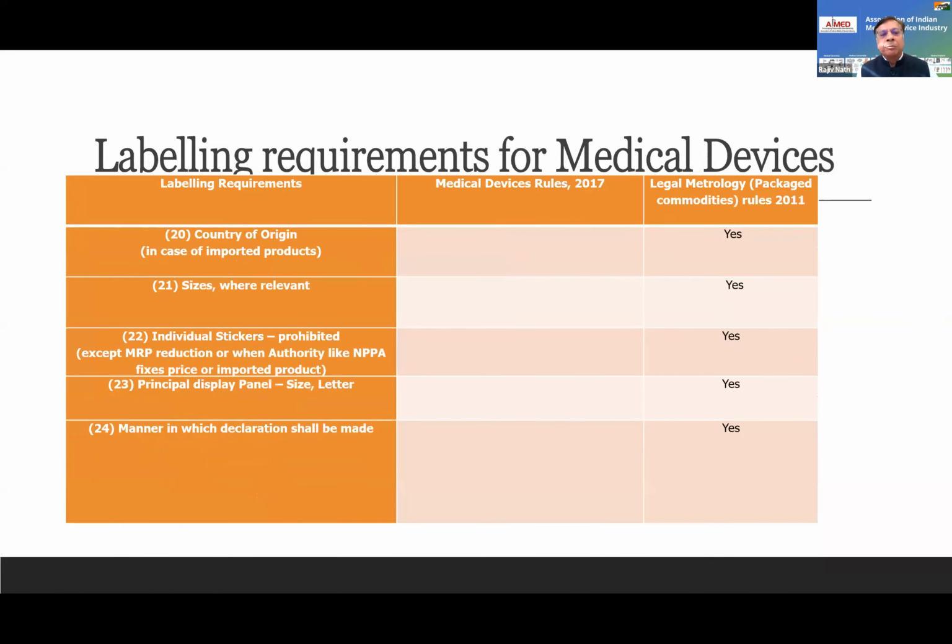Legal Metrology also demands additional requirements, such as country of origin. So just having the product with UK mentioned over there, having the address, is not country of origin. You have to clearly state it, because you can have an office in UK or an office in Germany, which is the selling place or the place of business, and it may not be the country of origin. It can be a transit point, because you also have different definitions in these countries, like the legal manufacturer definition.